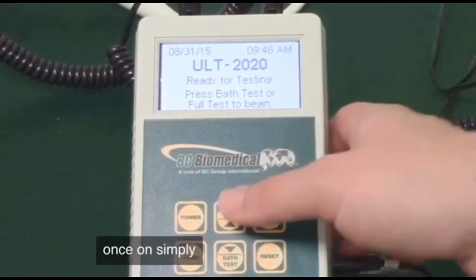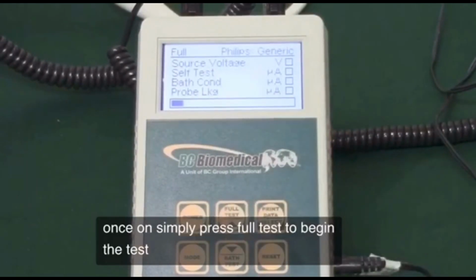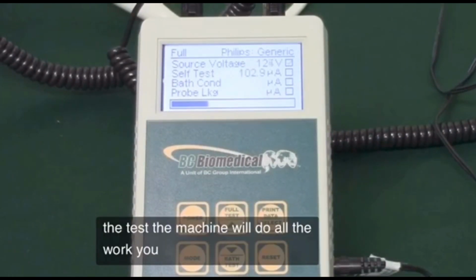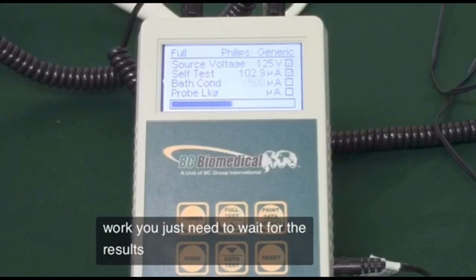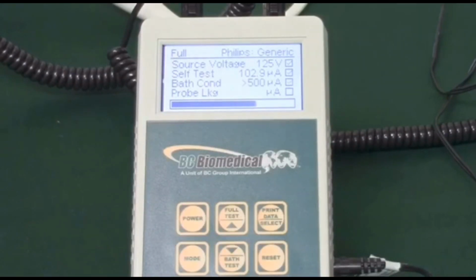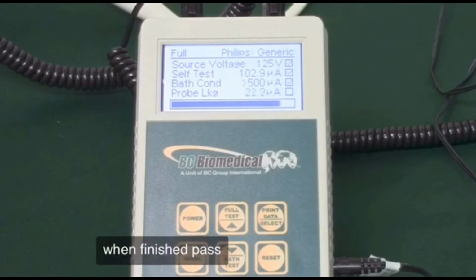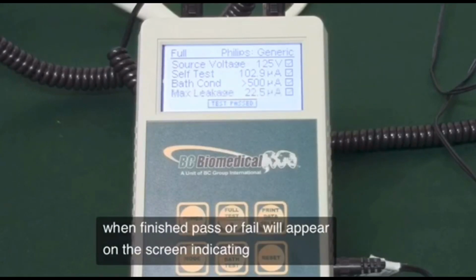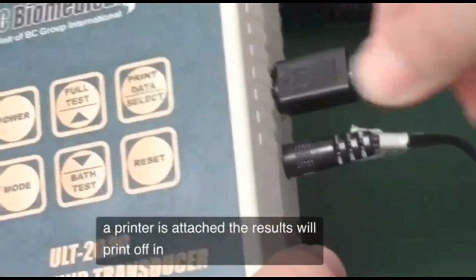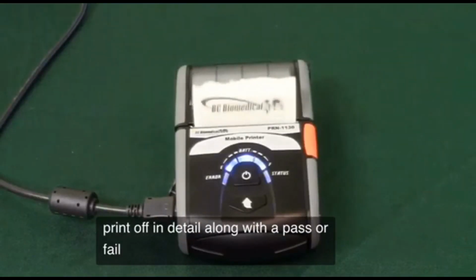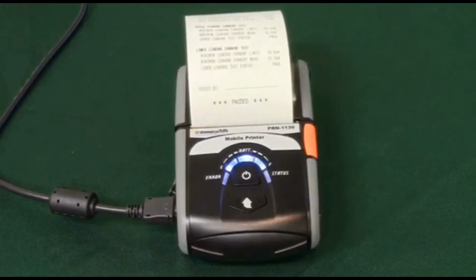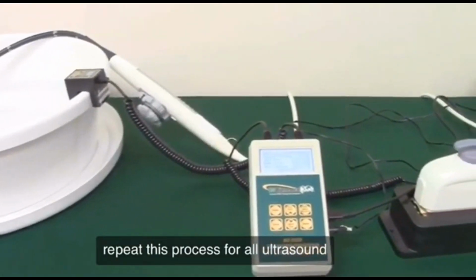Once on, simply press Full Test to begin the test. The machine will do all the work, you just need to wait for the results. When finished, Pass or Fail will appear on the screen, indicating your results. If a printer is attached, the results will print off in detail, along with a Pass or Fail. Repeat this process for all ultrasound transducers.